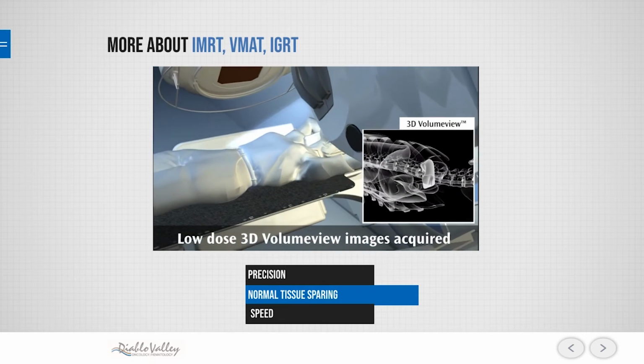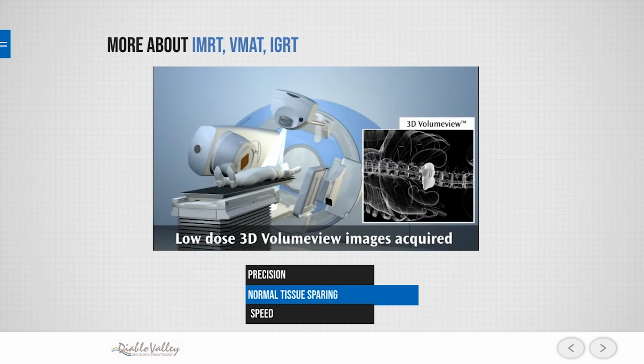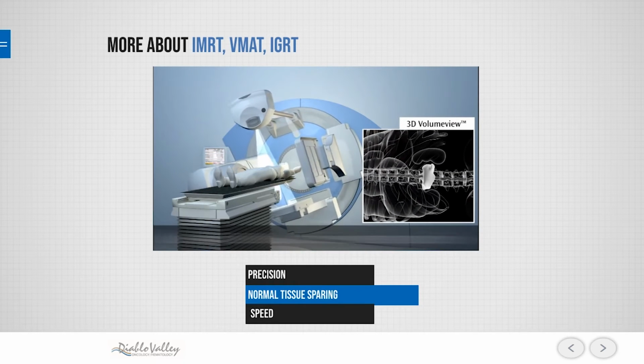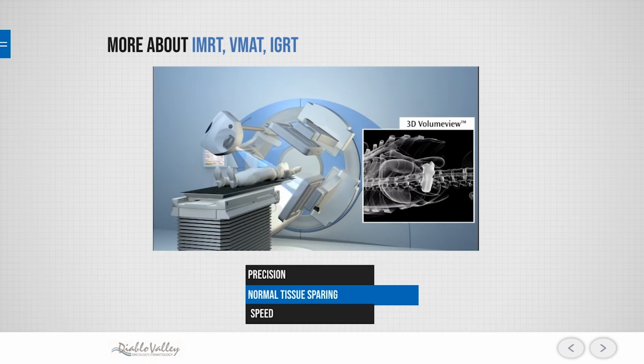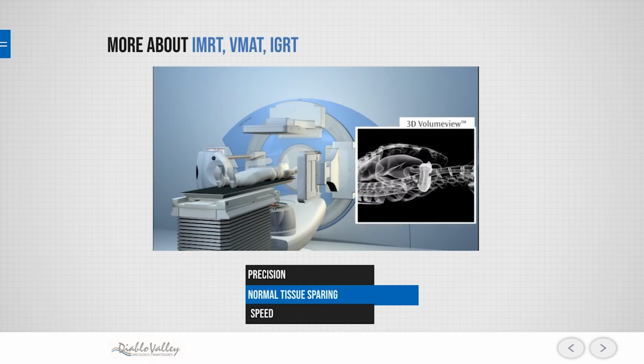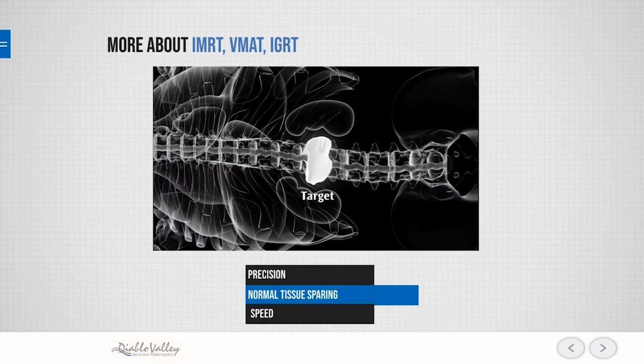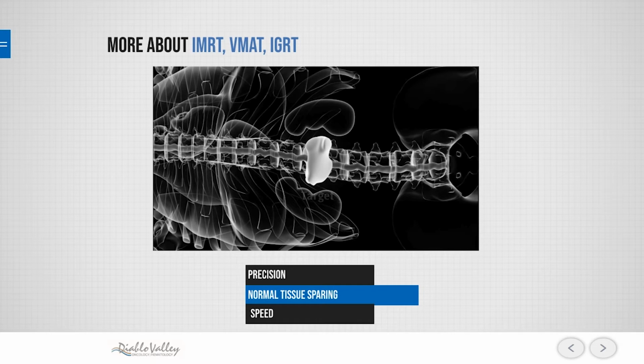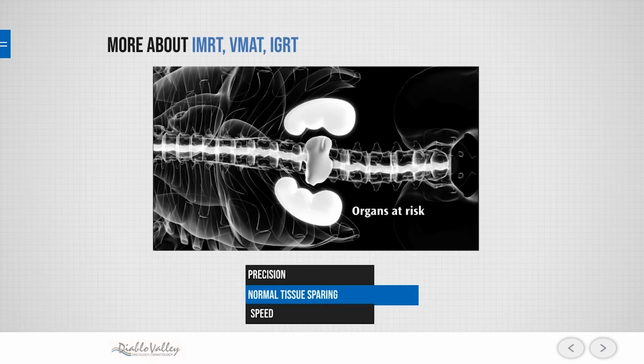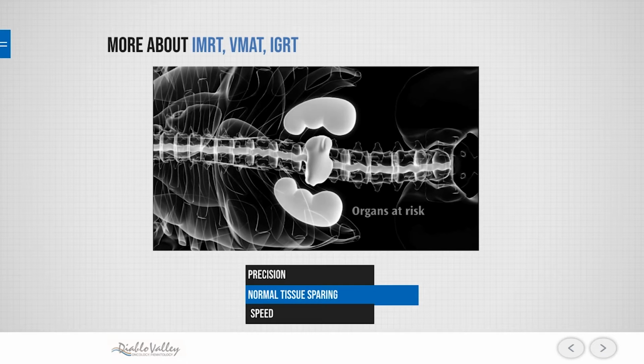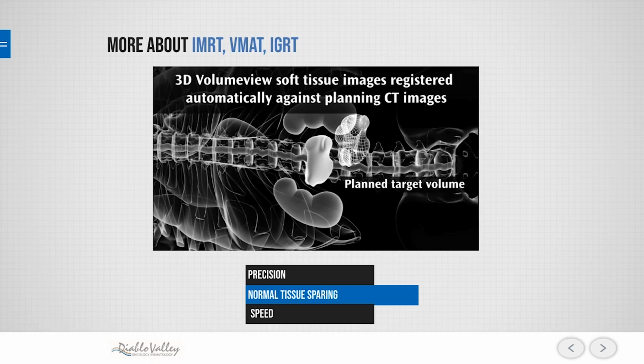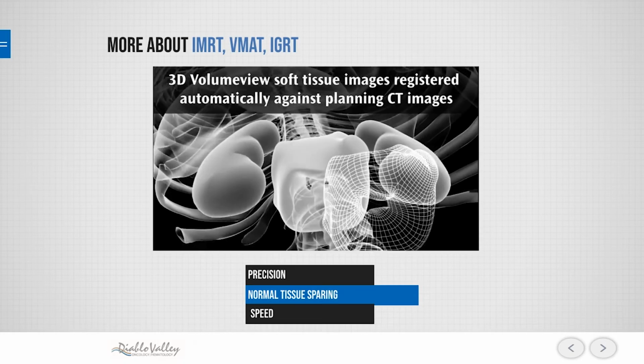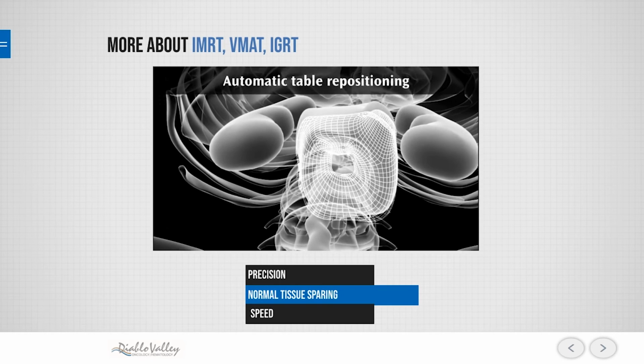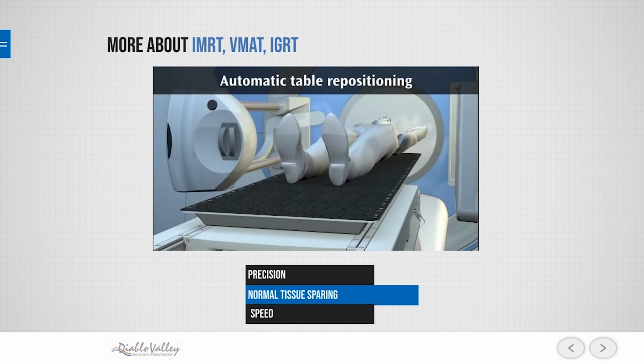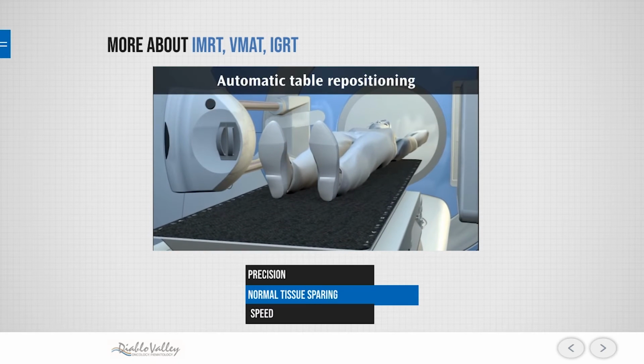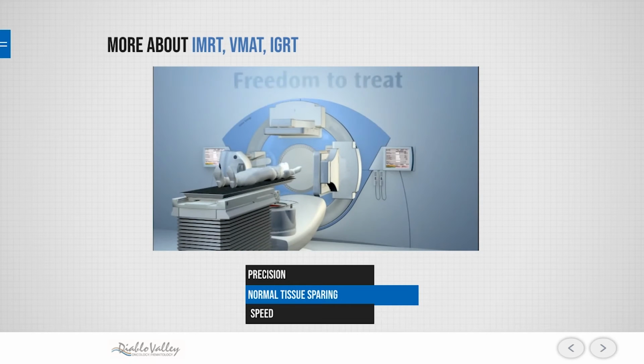The other advance is image-guided radiotherapy, which is what you're seeing here. Modern linear accelerators not only produce treatment X-rays, but they have arms that produce regular imaging kilovoltage X-ray beams, and they will allow us to actually create a 3-dimensional image, a CT scan in essence. This is a cartoon of a CT scan that looks nothing like a CT scan, but it allows us to see targets and normal tissues, and then we can in real time at the machine fuse that with our planning target volume. We can calculate subtle changes in translation and rotation of the patient and move them robotically into the correct treatment position. Most of our positioning systems for brain have an accuracy of plus or minus a millimeter, and even more accurate for stereotactic radiosurgery systems.